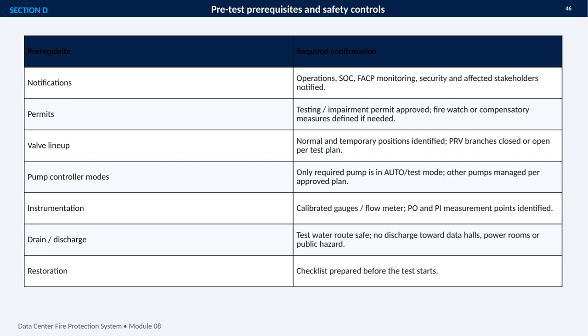Next, I need to verify the valve lineup, including normal and temporary positions, and confirm which pressure-reducing valve branches are open or closed for the test plan. Pump controller modes must be clear as well. Only the required pump should be in auto or test mode, while the others are managed according to the approved plan. Instrumentation must be calibrated, with the pressure observation and pressure indication points identified. Finally, the test water discharge route must be safe, and a restoration checklist must be ready before testing starts.